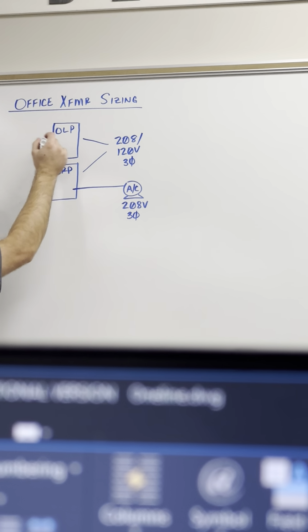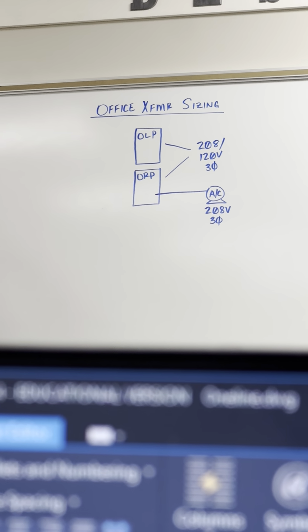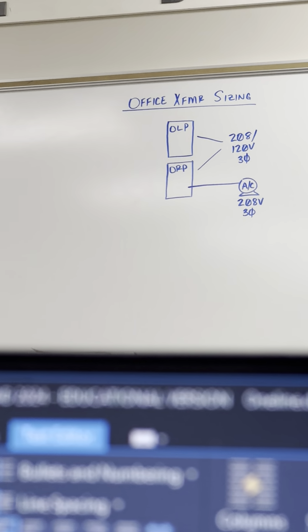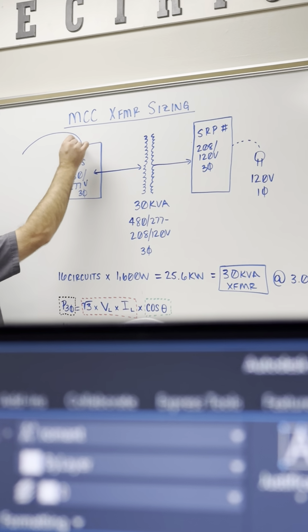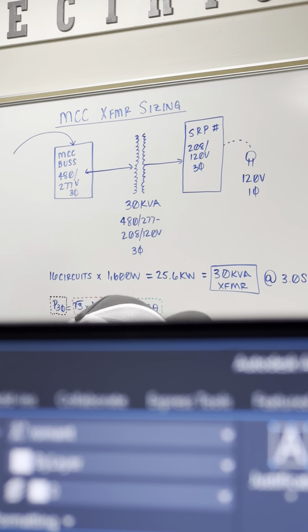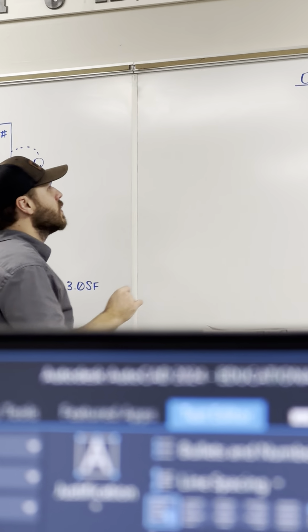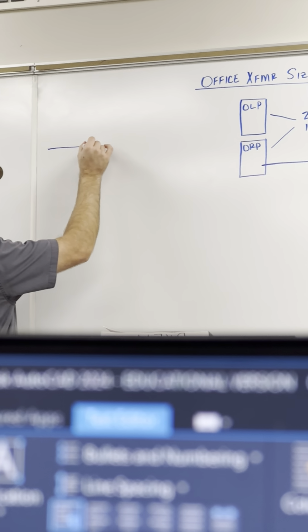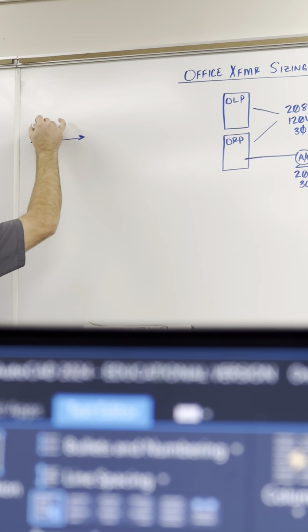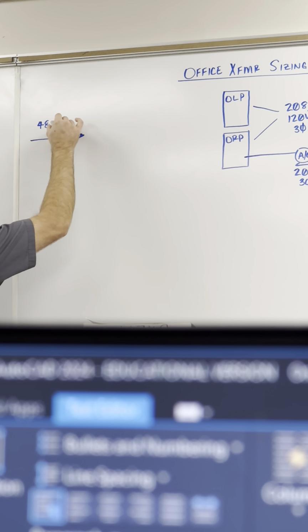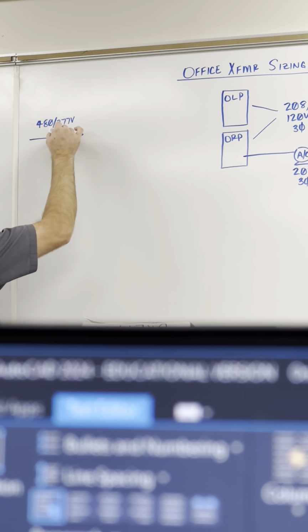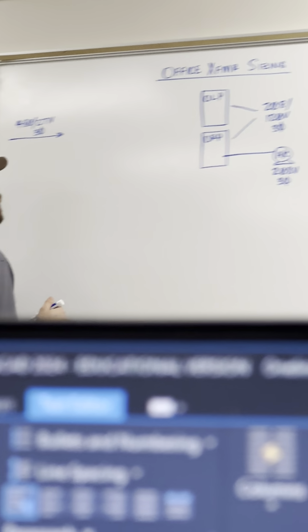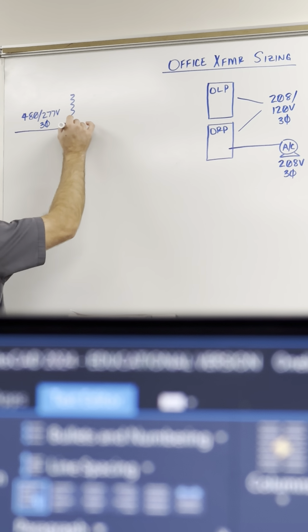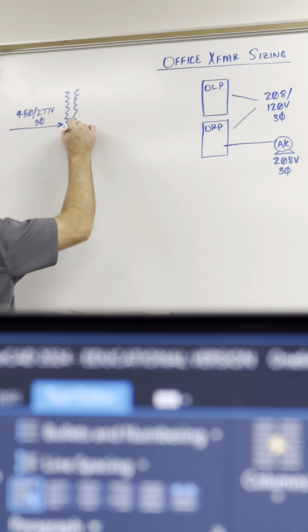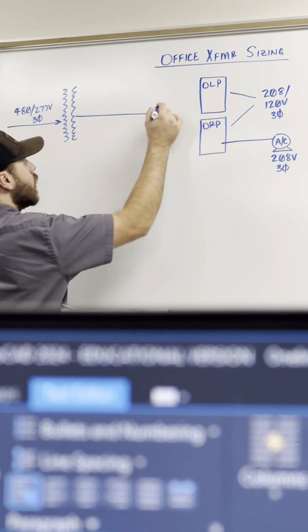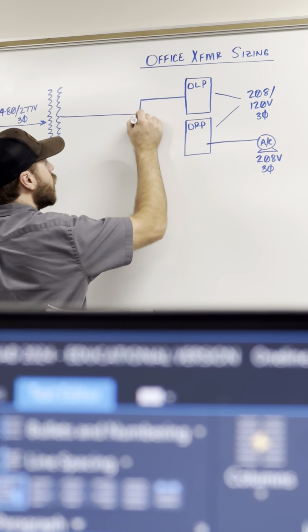How do these panels get fed? Kind of leading into a little bit of main feeders, all the wires that are gonna be coming in here to feed our MCCs, we're gonna have one that comes over here and feeds our office area. Similar deal: if our main feeder is coming in over here at 480, 277, and we got 208, 120 here, then we're gonna have a transformer to step that voltage down. And it can come over here, then it can feed our panels.